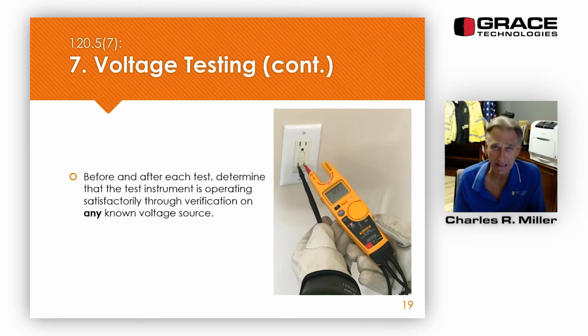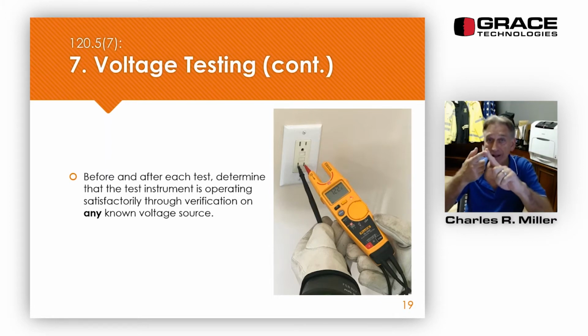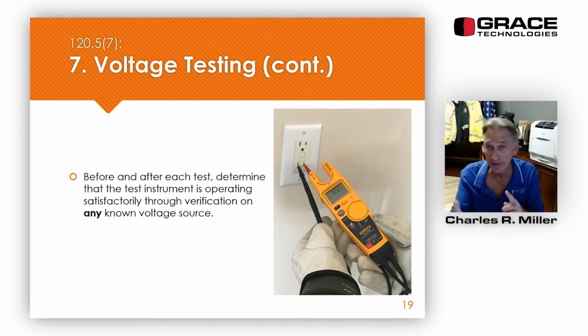You could check it on a battery. You could check your meter on a 9 volt battery, a AA battery, on any known voltage source. Now, what is not correct is to put it over in continuity and check the continuity part. No, we've got to be checking the voltage of the meter. And because it says any known voltage source, it does not have to be AC if you're going to be disconnecting AC, or DC if you're going to be disconnecting DC.